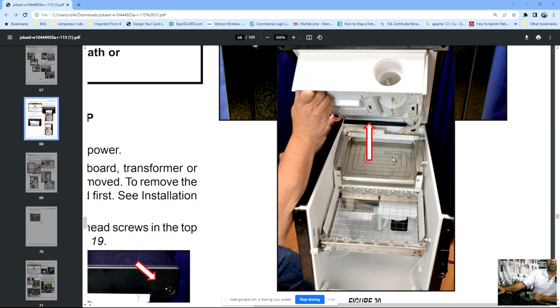I've run into a few of these ice makers, right here where my mouse pointer is pointing, where they arc weld them. I have seen that they got enough rust on that plate that it actually had a refrigerant leak. And it's sort of bad when that happens, because if we lose Freon, not only does Freon go out and we lose cooling, but this is the low pressure side, and running on 134, it's going to pull into a vacuum and possibly suck moisture into your evaporator and get water into your refrigerant system.